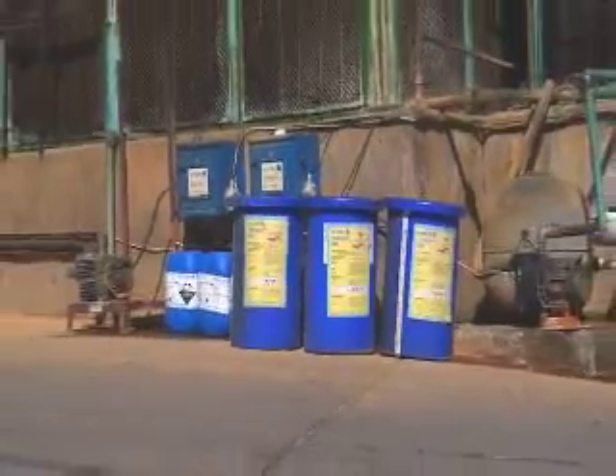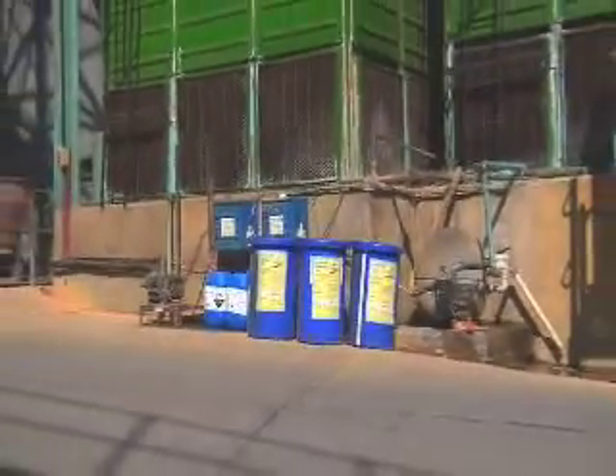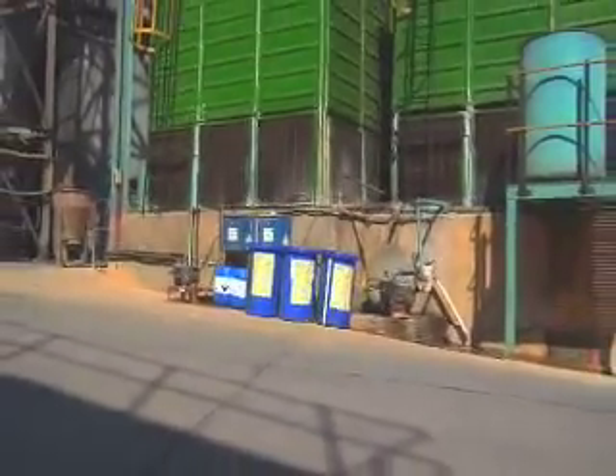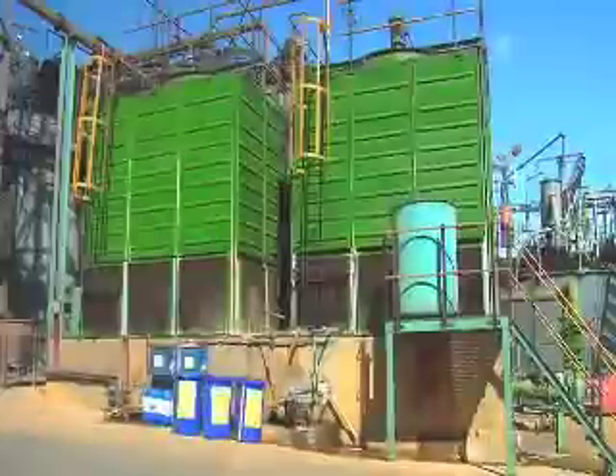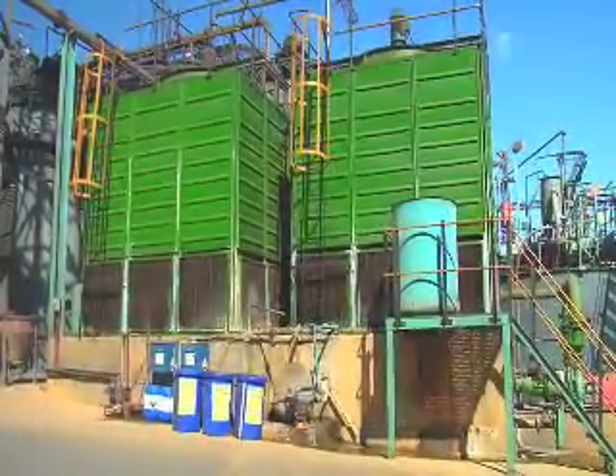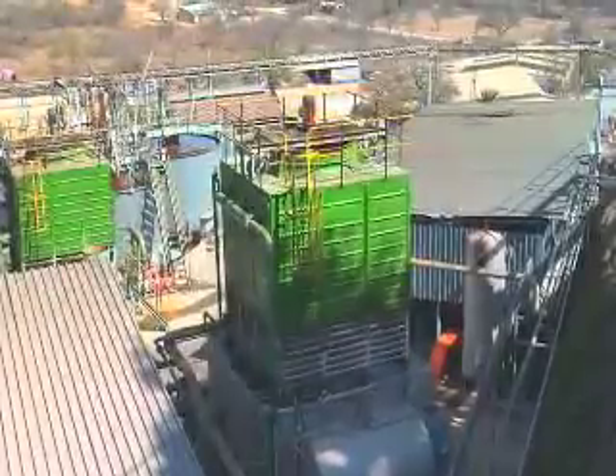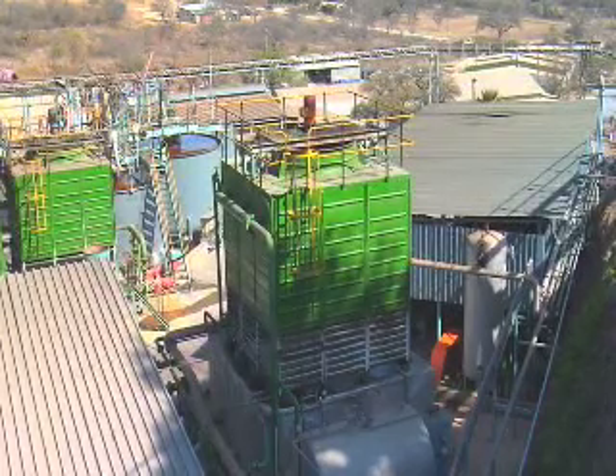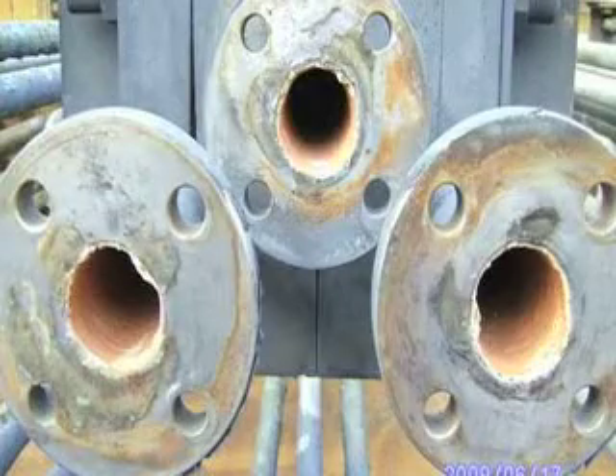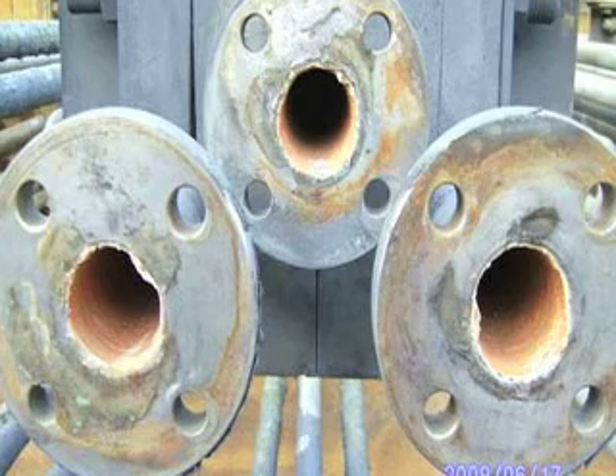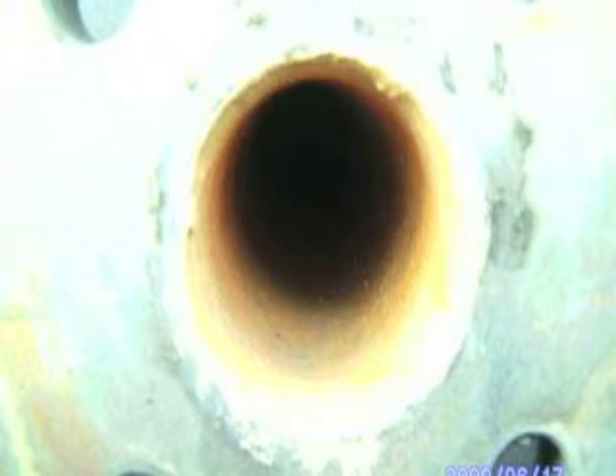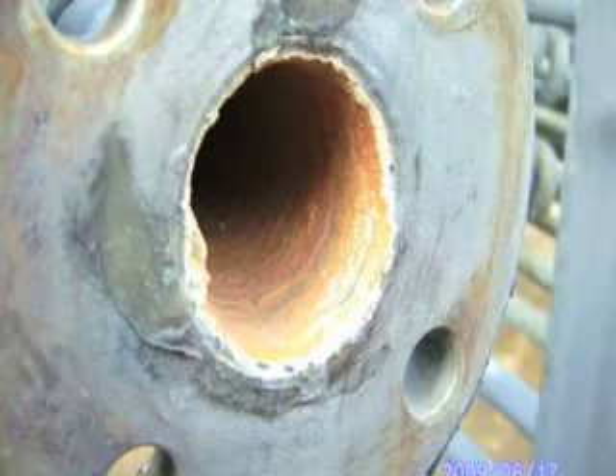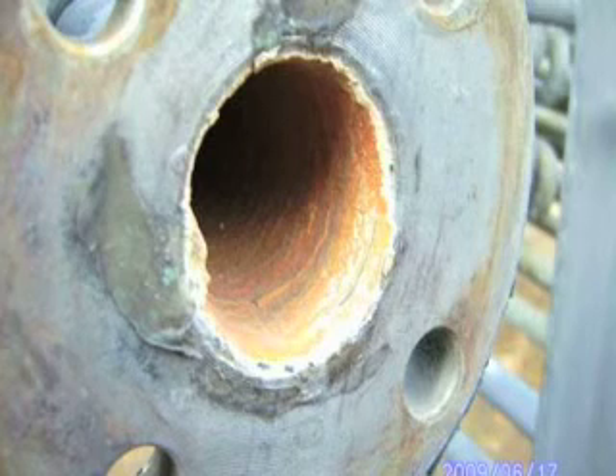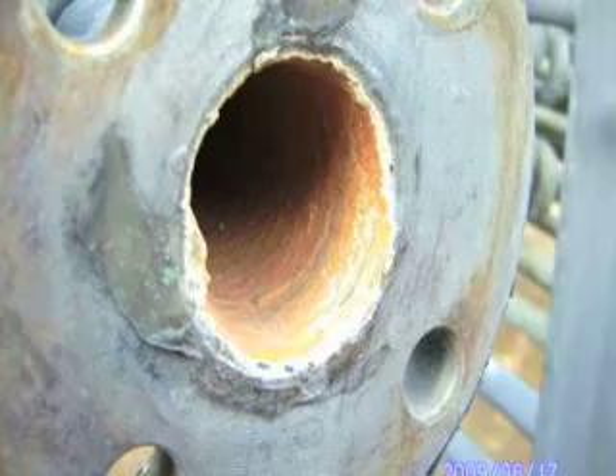In the past, the mine had to improve heat transfer and remove all the scale build up during a period. They had to periodically fill a drum, lift it up to the tank, connect each of the cooling coils into the Savtox drum and circulate the Savtox through the coils in order to remove all the scale. As things are now with the WESU system, this will not be required anymore.